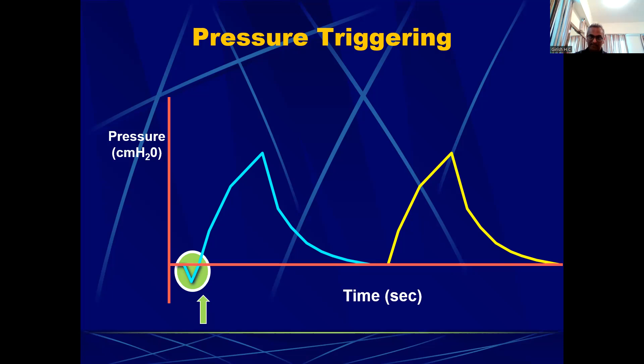Clear? Yes. Okay. Now, pressure triggering was the first to come actually. It needs less technology, and the ventilators with pressure triggering were less expensive, whereas flow triggering is a little more complicated and more technology driven. So it is more expensive, but most of the modern ventilators nowadays have both pressure and flow triggering. Before you buy any ventilator, you should always ask whether it has flow triggering, but most modern ventilators do. I'm not saying one is better than the other, but theoretically flow triggering is much better compared to pressure triggering because it is a much faster triggering mechanism. So how does flow triggering work? For flow triggering to be understood, look at this diagram.